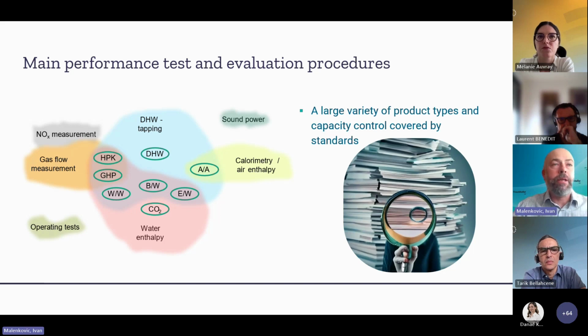Hydronic systems are tested according to the water enthalpy method, meaning you evaluate the heating capacity and the COP or EER, the efficiency of the heat pump or chiller, from the supply temperature, the return temperature, and the mass flow - so from the energy output of the heat pump and the energy input, electricity or gas, into the heat pump. I won't go into the details.